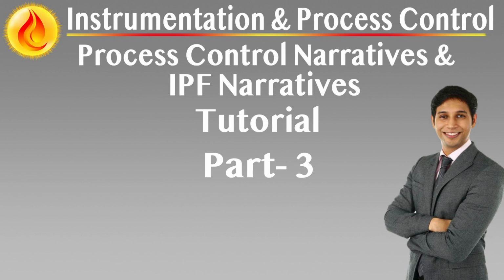Consequence of no action explains what would likely happen if the alarm is ignored or not acted upon promptly. This includes possible effects on product quality, e.g. off-spec material, equipment damage, e.g. pump cavitation, overheating, process safety, e.g. buildup of pressure or risk of release, environmental or regulatory compliance. This helps prioritize the alarm and determine whether it requires immediate attention, planned response, or escalation to automated shutdown.